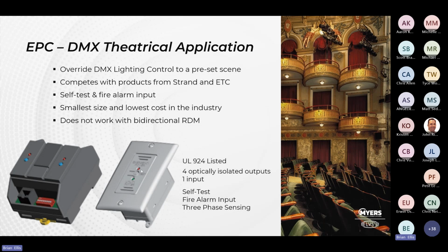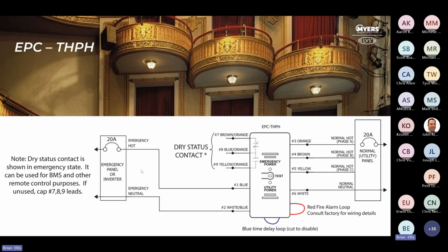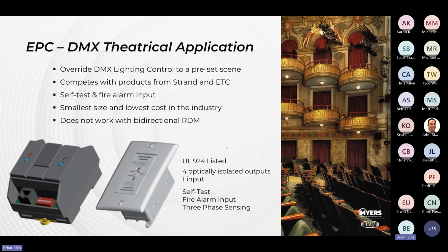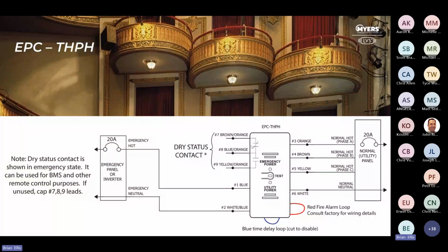This device allows us to tie in all the phases of utility and a neutral so that we can monitor all 3 phases. When any dropout, automatically we go to this preset level, but this device can also be used to send a contact closure or an open to any other device that you guys might have. So one of the things with being an LVS rep, you guys have different conglomerates. You have different lighting control products, all of this, and right.